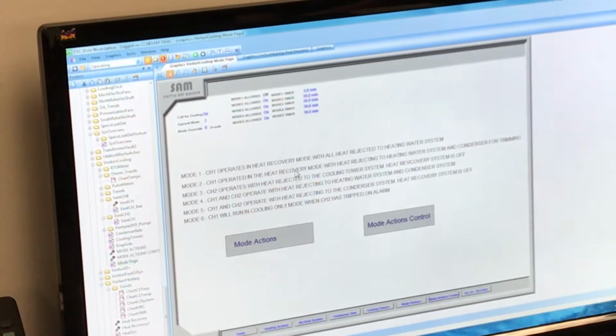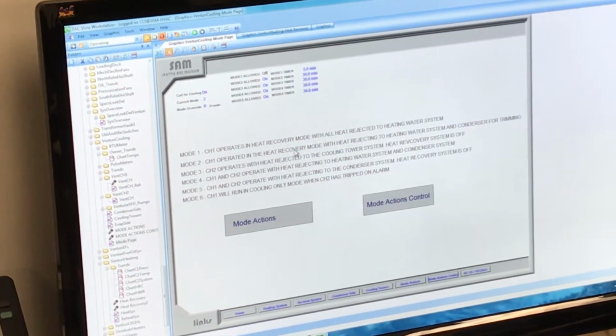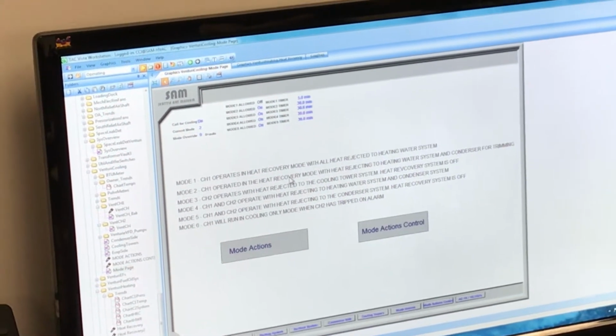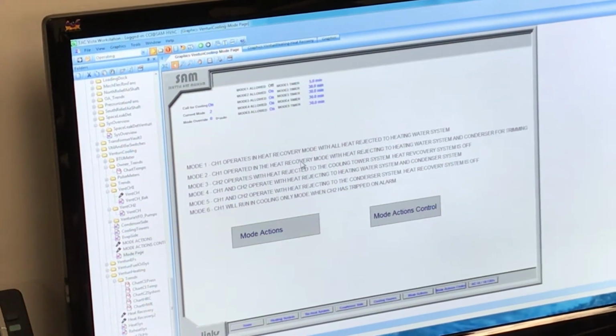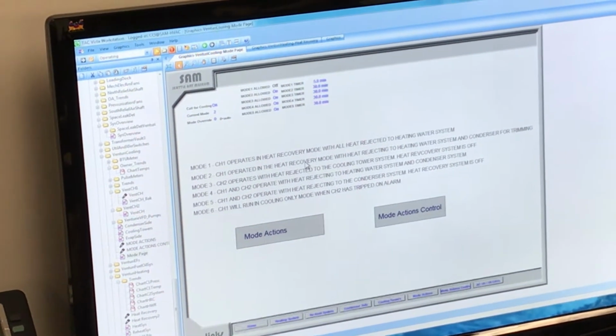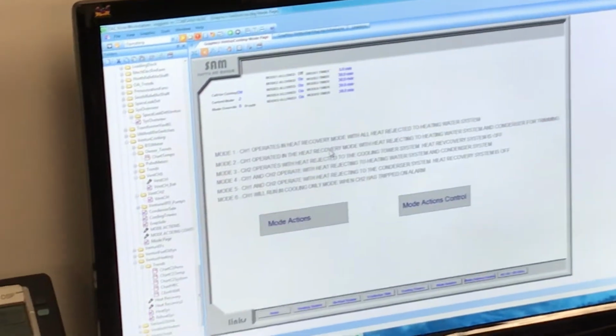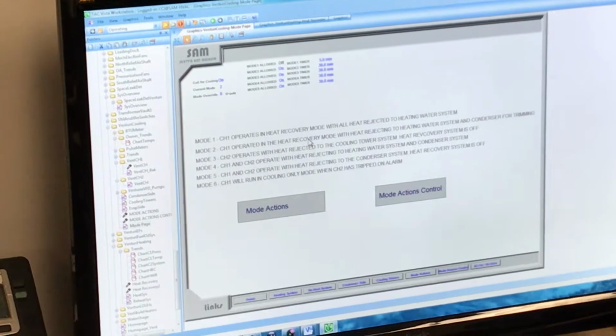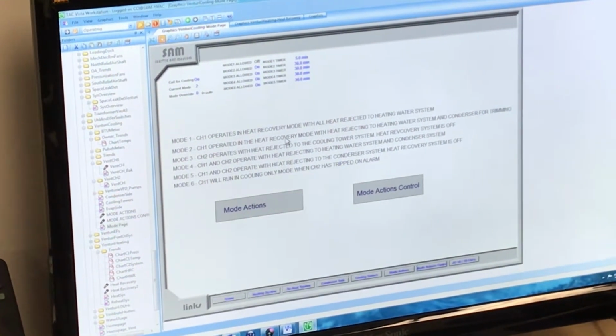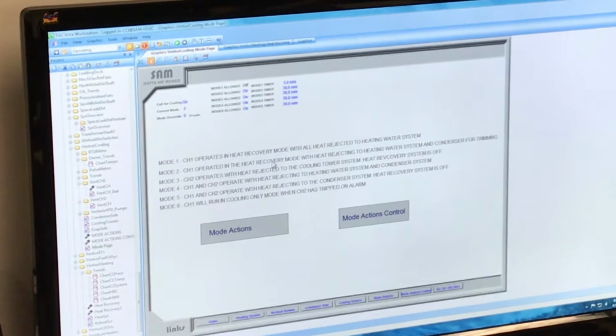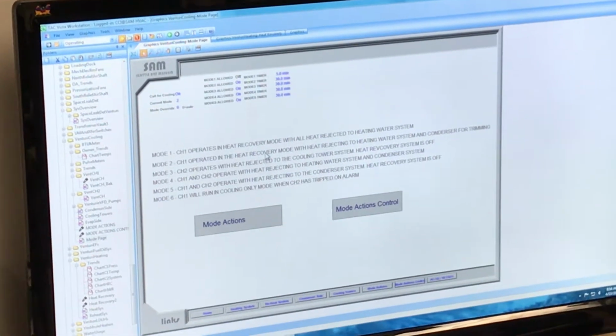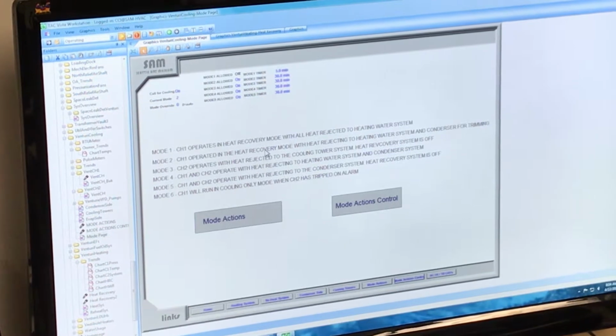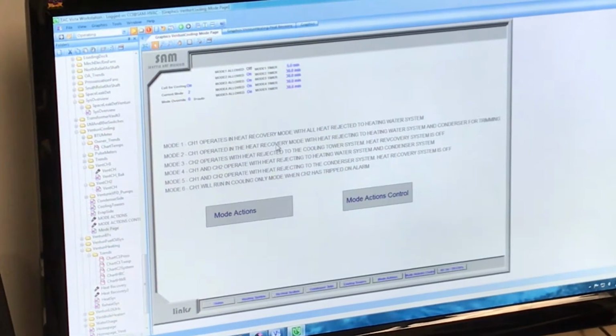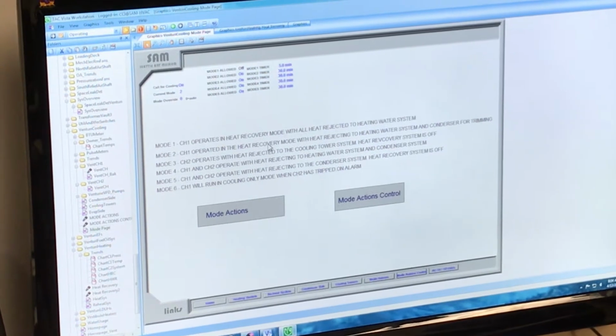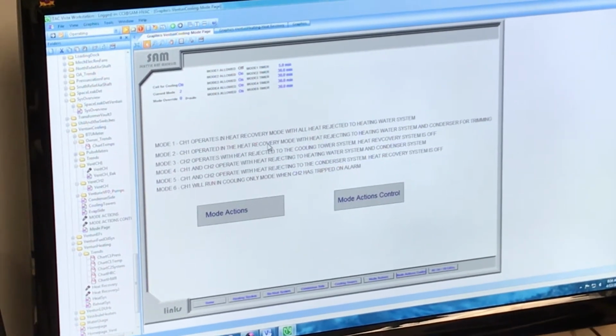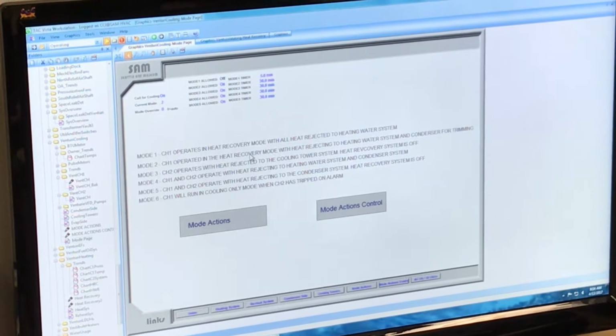So it didn't really directly send to the cooling tower. There is a heat exchanger, and the condenser loop actually goes through the heat exchanger. So what the system is doing is that there is a three-way valve trying to moderate the temperature, and if the leaving water temperature gets too hot on the condenser side, the valve will open so that water will go through the heat exchanger, and the heat exchanger will put some heat out to the cooling tower, which will be always running, whether the valve is open or not, so that you can reject it at any time.